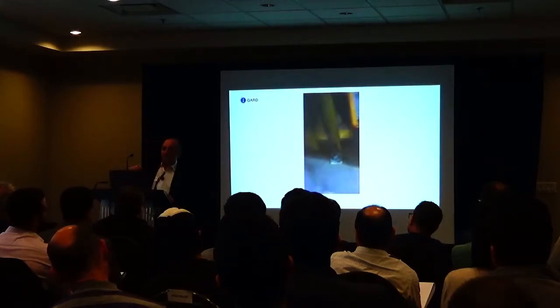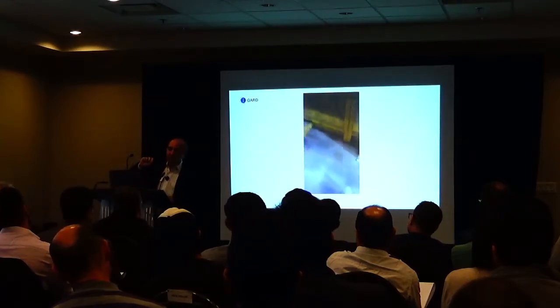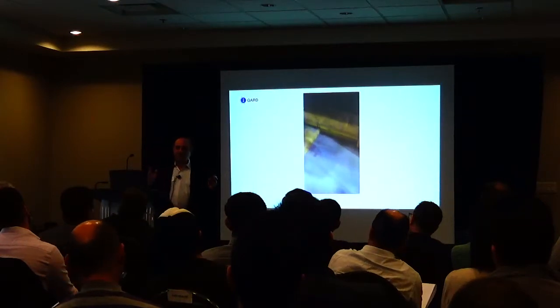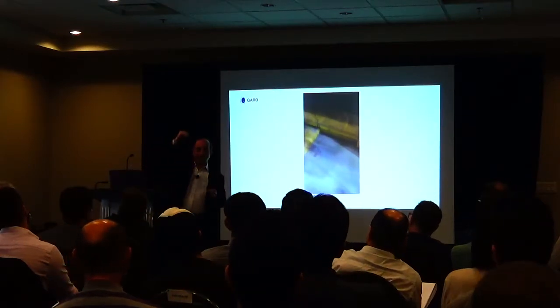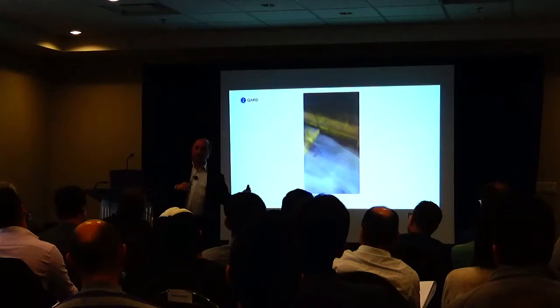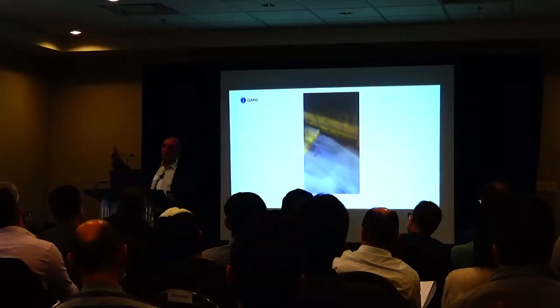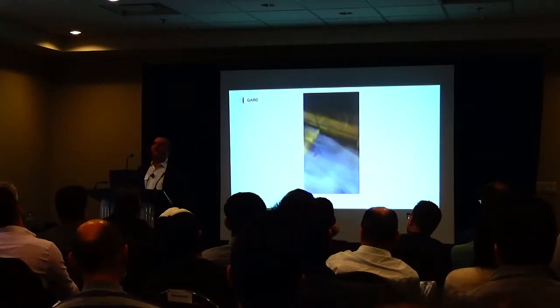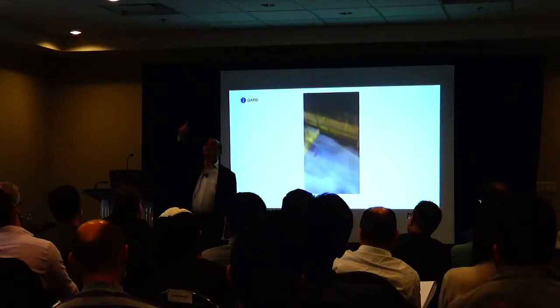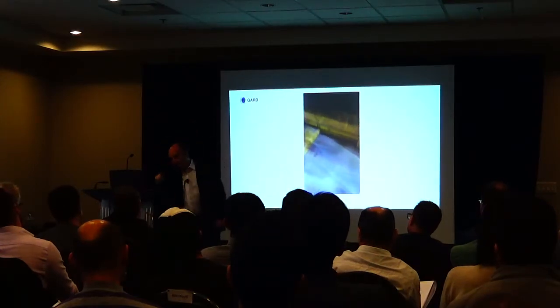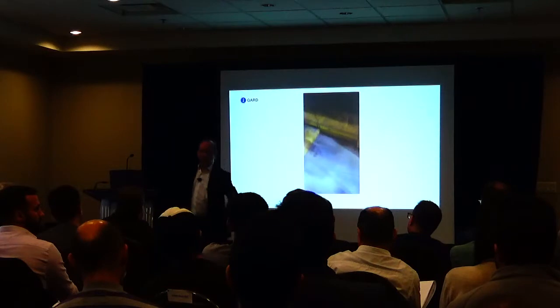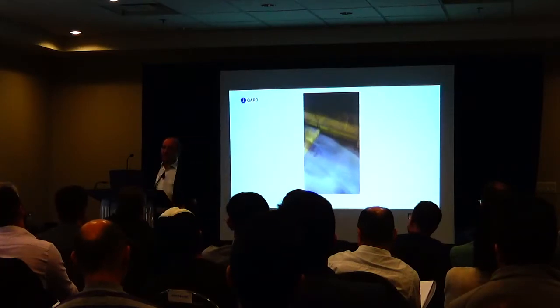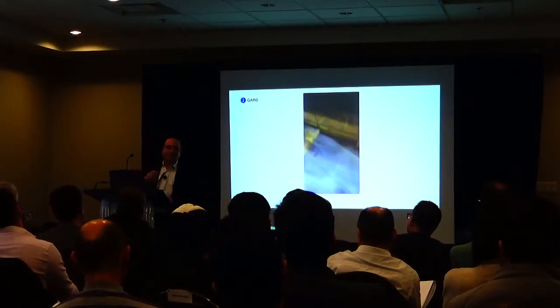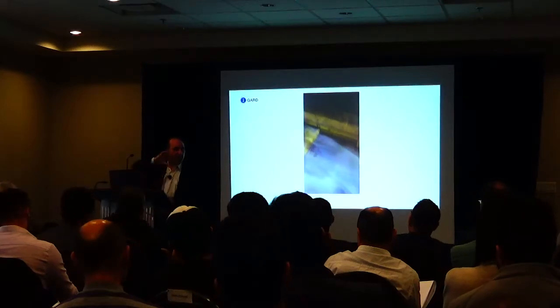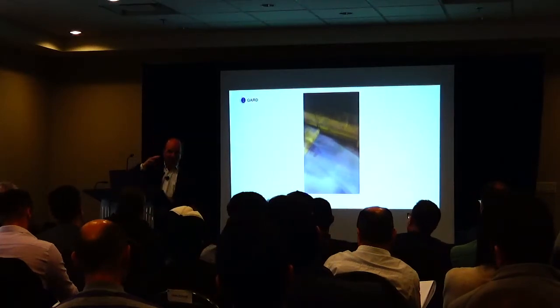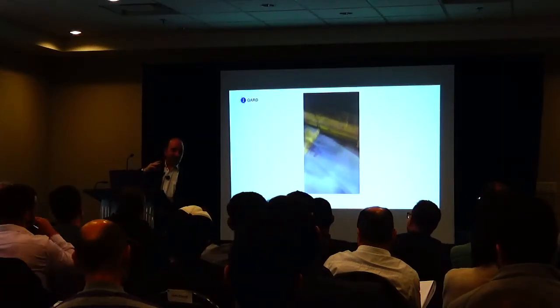And I've been to some facilities where they actually label the conduit. Say for example, you're at an MCC. They label the conduit exiting the MCC, which bucket it's coming from, and what motor it's going to. So I don't have to say, okay, let's open the bucket, look at the cable tray. It's this one, it's this motor right here. Right? Because what you want to do is create a safer environment. So your conduit is labeled. It takes a lot of effort to do that.